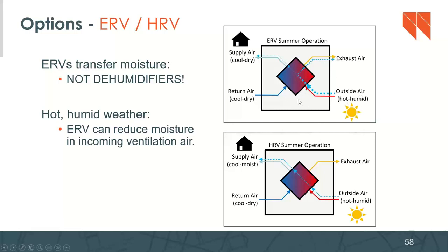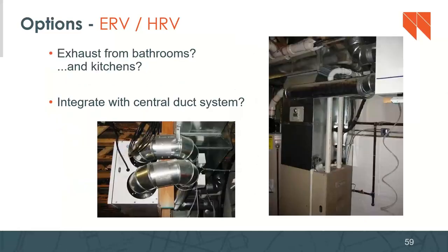With the ERV summer operation, if the inside air is cool and dry and the outside air is hot and humid, a portion of the humidity in that outside air could potentially be redirected outside. Only if your inside air is drier than the outside air. So that's the caveat. That's why on the next animation, it says it depends. Okay. I hope that was not clear as mud. I hope it was somewhat clear. If anybody has questions, we can go back to it and talk through it. Okay, let's talk about some system layouts and some options for the ERV, HRV.